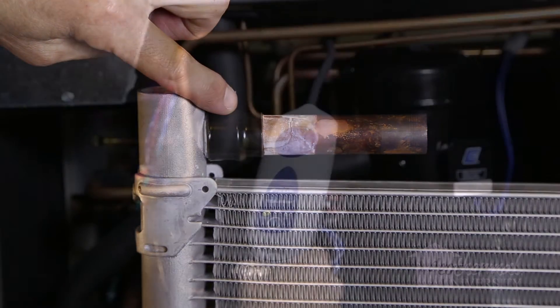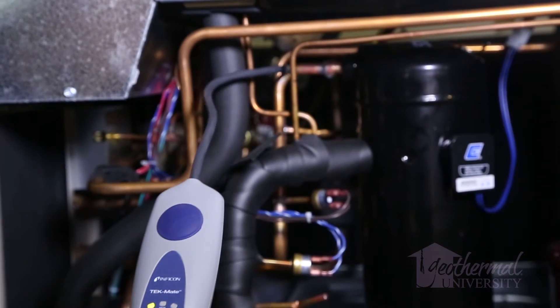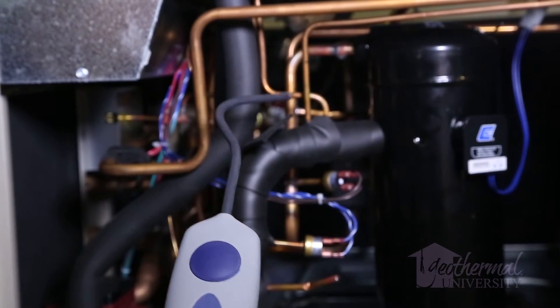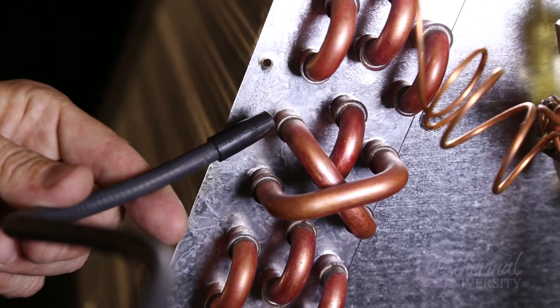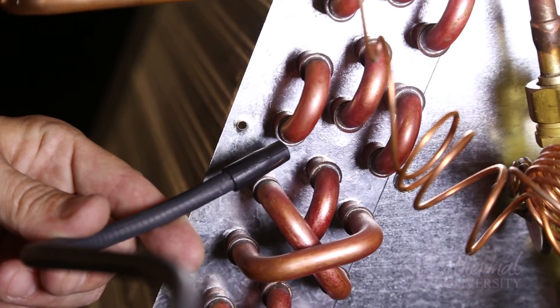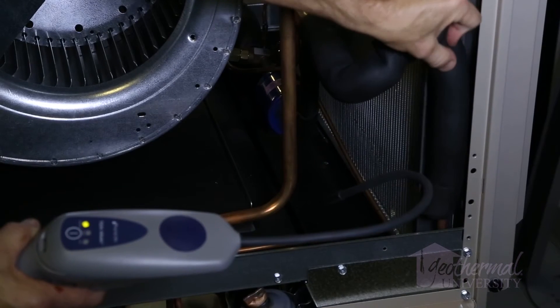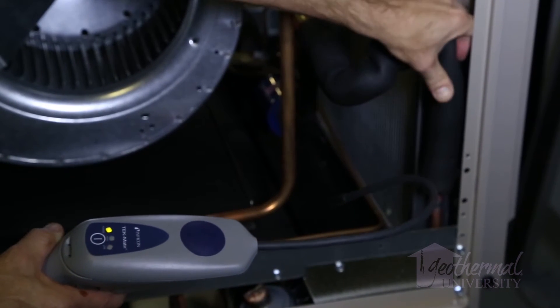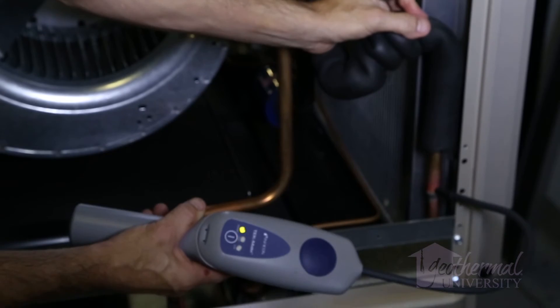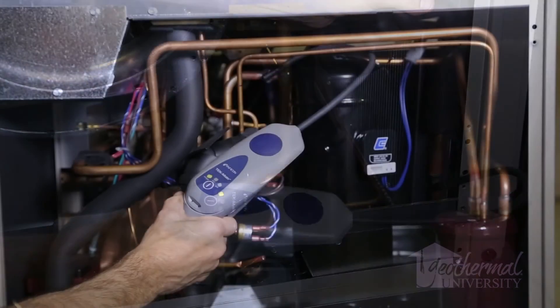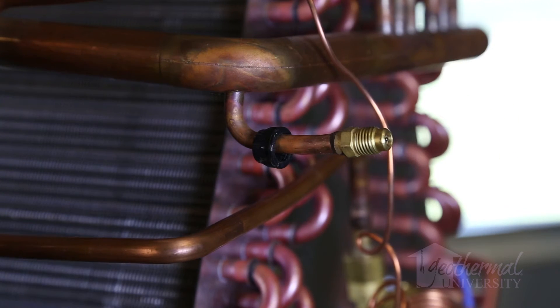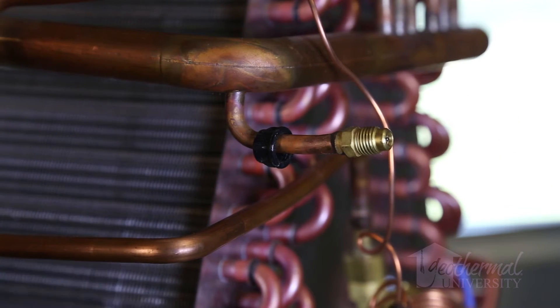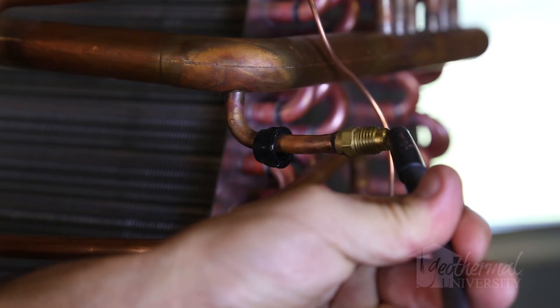Inspect any couplers for pressure switches and gauges. Remember, a copper aluminum coil has return bends on the backside of the coil. There are usually a significant number of braze joints on the aluminum-copper coil. Peel away any insulation that's covering a joint or connection. Inspect all tubing connections, such as equalizer lines and tubing, and remember to look for oil or dust buildup. Remember to inspect the Schrader ports. We often overlook leak detecting at the ports because our gauges are connected. You'll want to leak check the ports with the caps off.